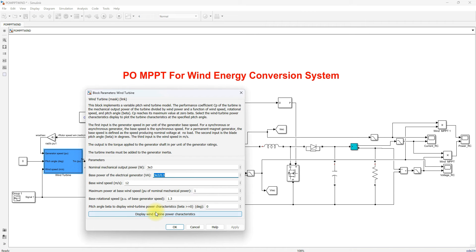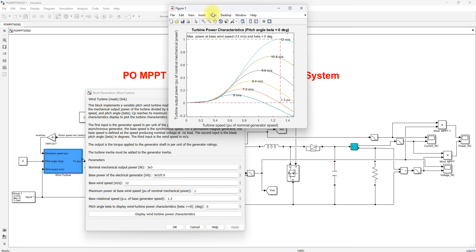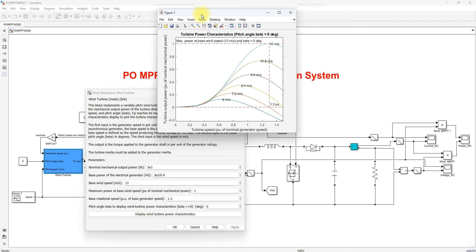The base rotational speed is considered as 1.3 per unit. Here you can see the turbine output power with respect to turbine speed for different wind speeds. When the machine is operated at 12 meters per second, we get 1 per unit — that means 3 kilowatts of power from the wind turbine. When wind speed changes, the peak power will be varying.